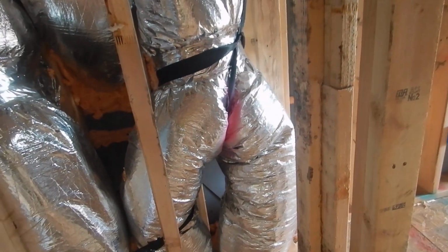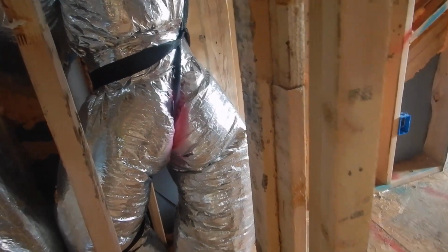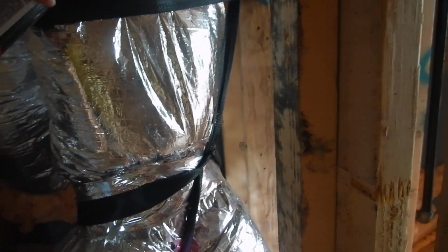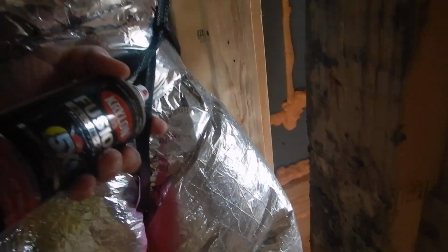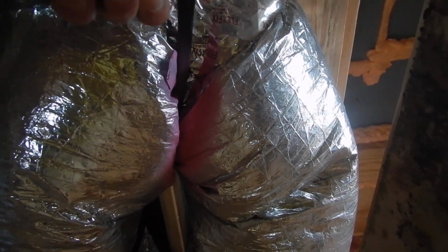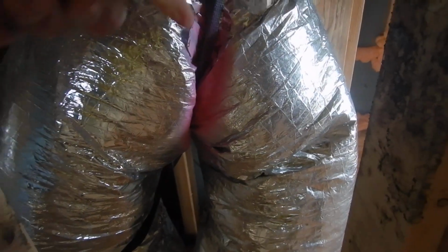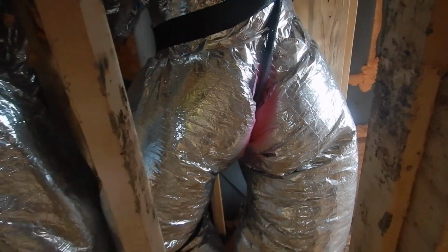And then we're going to roll over here. Air duct should not be touching other air duct. It's going to condensate and fall down on the floor. Air duct should not be kinked. When you have this nylon webbing, this is like the elastic in a cheap pair of underwear. Is that going to cut into your air duct? Looks like it's cutting right into it. Is that going to restrict your airflow? You bet it is. So that's what we got.